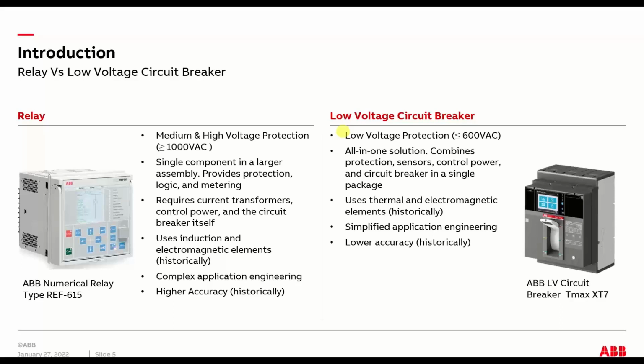Whereas a relay provides only the smarts for the system. It's only the protective functions and maybe some logic for control, maybe metering, but it's not the circuit breaker, and it's not even the sensors. In a low voltage breaker, the circuit breaker, the sensor and the breaker mechanism all come together as one big package. So the relay requires sensors, which are typically current transformers, and control power. That's another important thing. They're not self-powered. You need some sort of reliable power source, battery or UPS, just to have the protection system work at all. And then the circuit breaker itself.